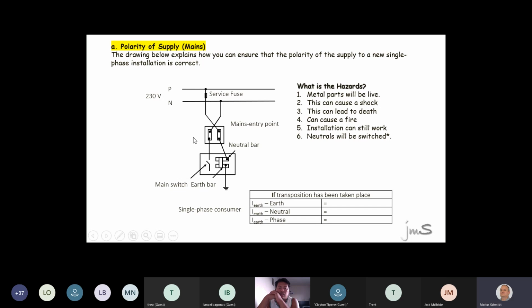See there? Now my question is, because this is live, there's only one way to do it. You use yourself a remote earth, a trailing lead, and a voltmeter. What voltage are you going to measure when you touch metal? Didn't I say the metal part becomes live? 230. Right. Independent earth, 230. Well done, Vincent. What are you going to measure between earth, independent earth, and the neutral? 230. What are you going to get if you measure between earth and the phase? Well done. You guys are writing good answers down.